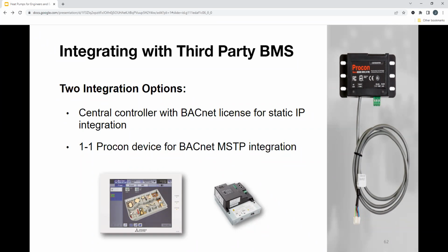And then you're also able to do an MSTP connection using a small Procon device, BACnet MSTP. Typically with this, it's a one-to-one connection at the indoor unit control board, and hardwire that to the BACnet. Typically with this, you might use it on maybe a project with 10 fan coil units. Anything above that, you probably just want to go the central controller route.